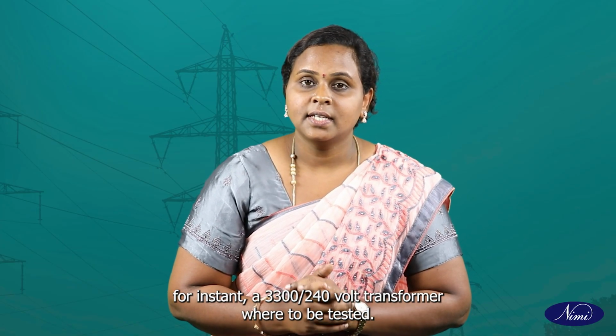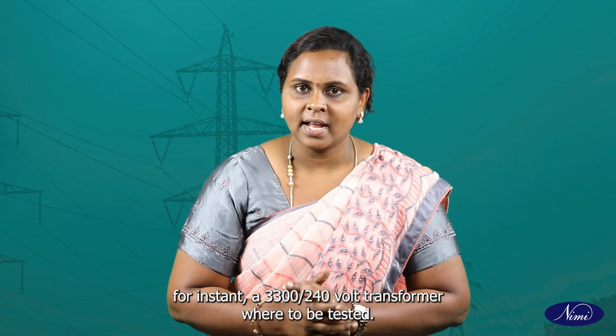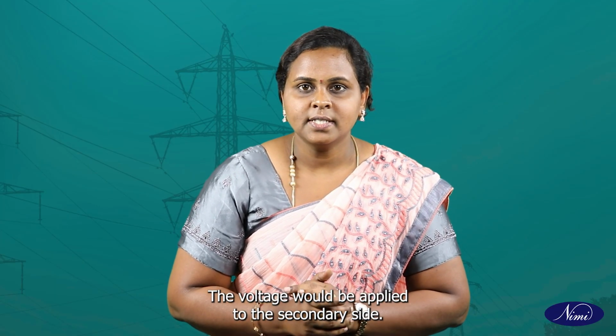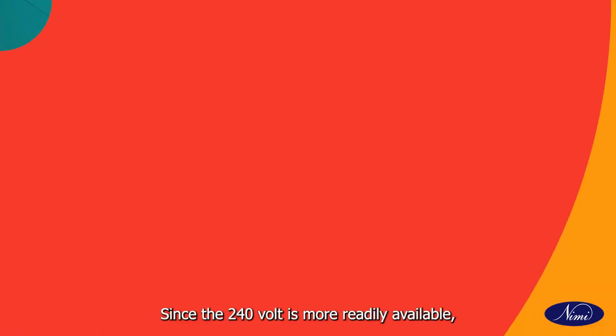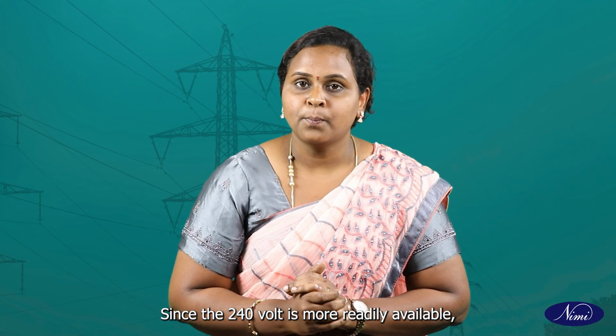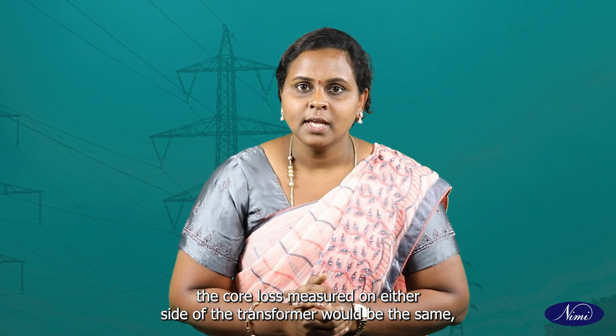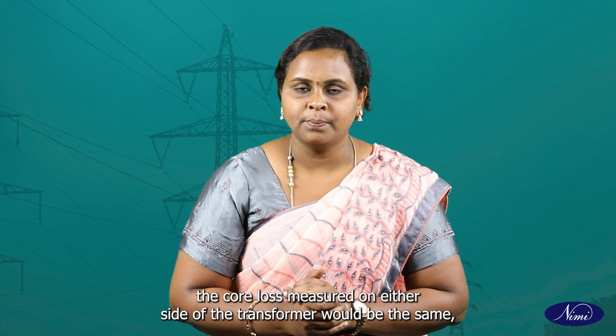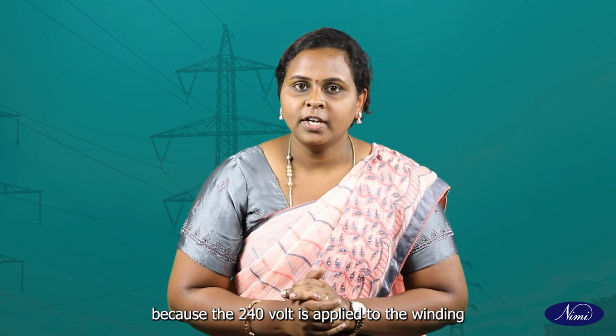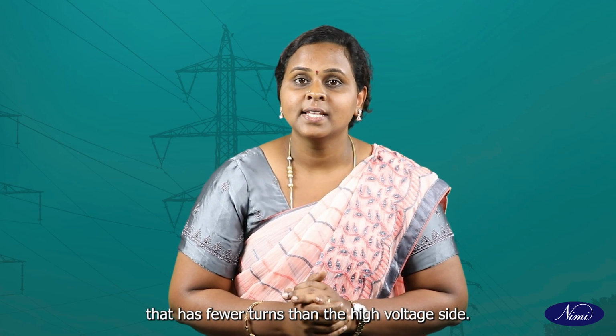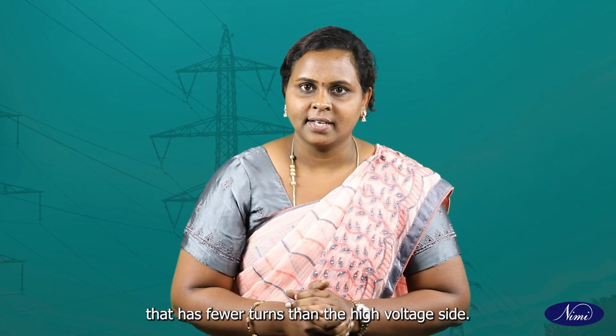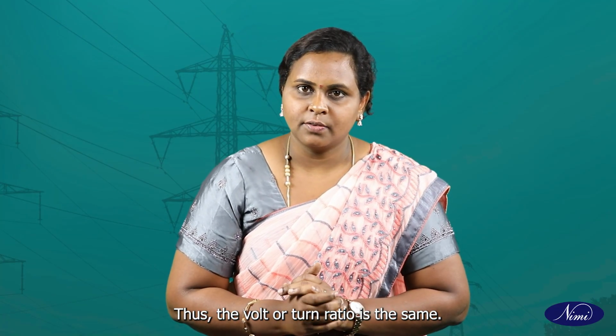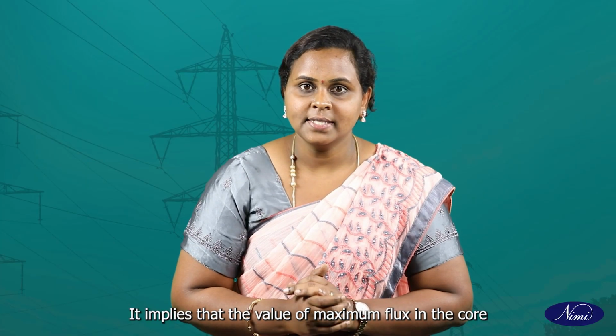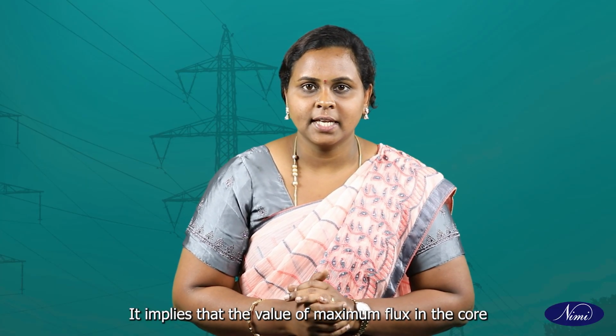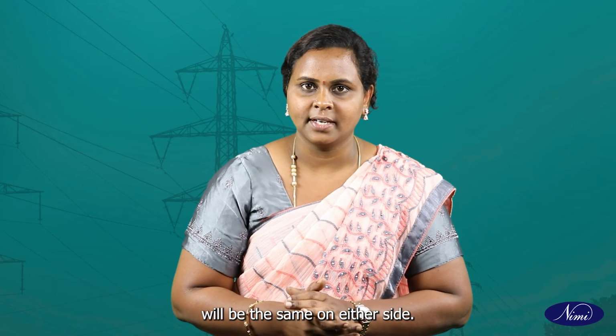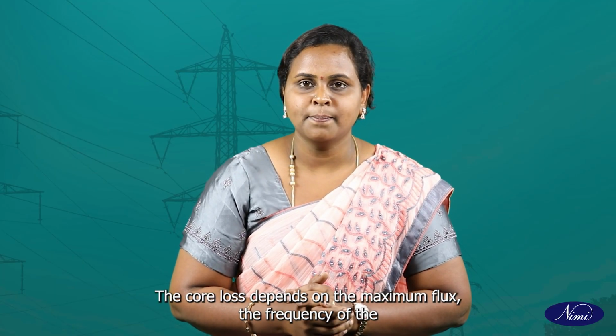For instance, if a 3300/240 volt transformer were to be tested, the voltage would be applied to the secondary side, since 240 volts is more readily available. The core loss measured on either side of the transformer would be the same, because the 240 volts is supplied to the winding that has fewer turns than the high voltage side. Thus, the volts per turn ratio is the same. It implies that the value of maximum flux in the core will be the same on either side. The core loss depends on the maximum flux.